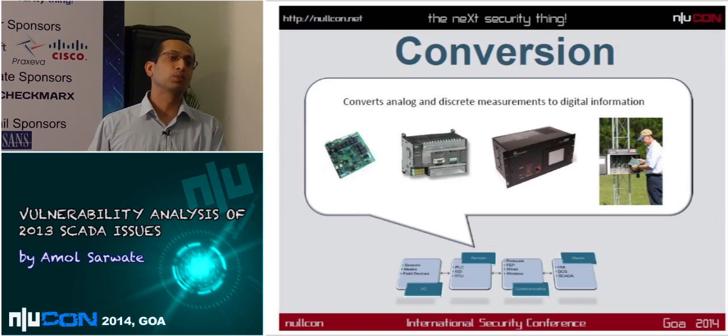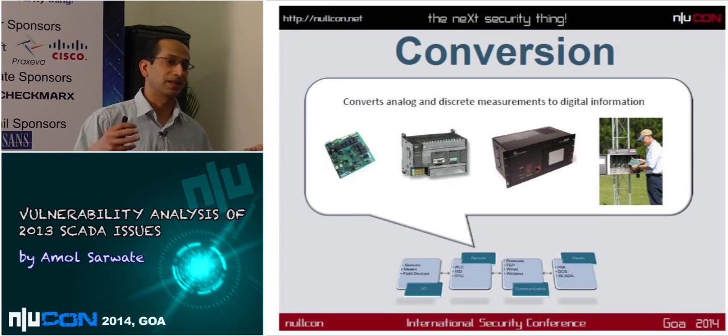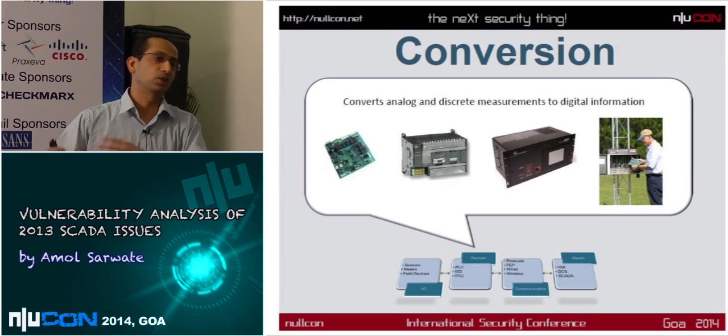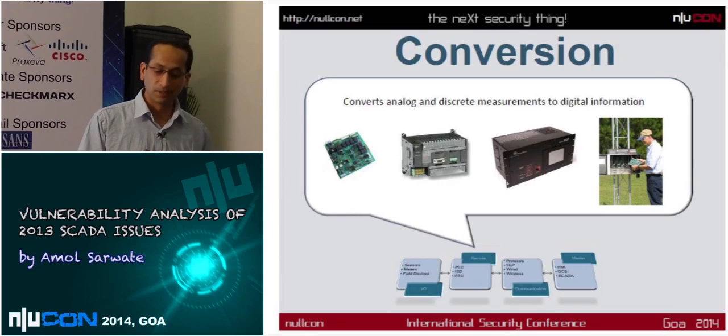Now they are just ported to TCP/IP. For example, with Modbus, what they have done is put the entire Modbus packet into a TCP packet, and that's why it runs on TCP/IP. But a lot of these protocols do not have security built in such as SSL or TLS, and that is a pretty common, pretty easy attack vector.